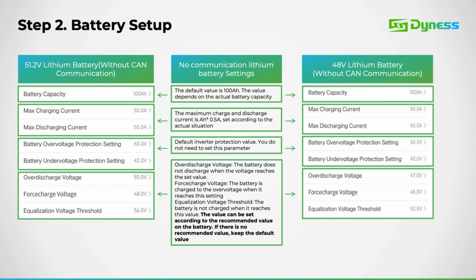When opting for the lithium battery without communication, these are the settings you'll encounter. This is particularly crucial since this battery type operates on voltage logic, requiring precise information in line with your battery specifications. Additionally, with this battery type selected, both over-discharge and force charge settings are determined based on voltage logic, unlike the previous mode, which relies on SOC.